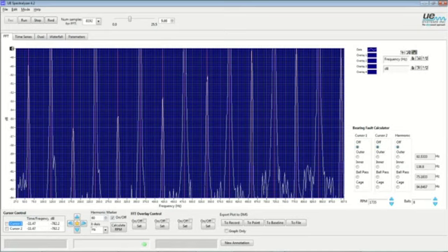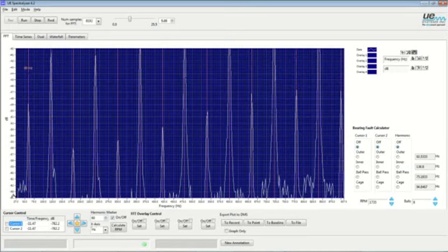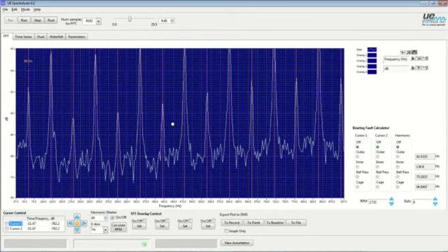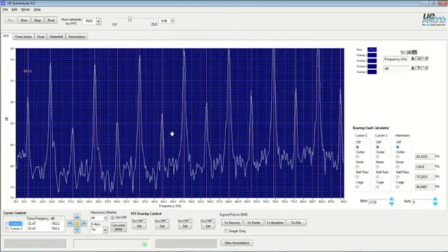Now, in that recording, some of us may be familiar with that sound, and it's normal for most transformers to hum like that, if you want to call it humming. But look at our frequency spectrum. We have a very characteristic pattern here as it relates to transformer hum combined with vibration.